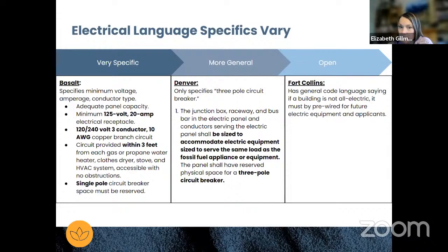And then once you get over 4,000 amps, you do have to have additional physical space. As of today, no one has had any success getting greater than 4,000 amps in a single transformer cabinet, even if you could physically fit a larger capacity transformer within that cabinet. So it is a bit of both. I wouldn't want to negate the physical space, but I think they're tied, if that makes sense.